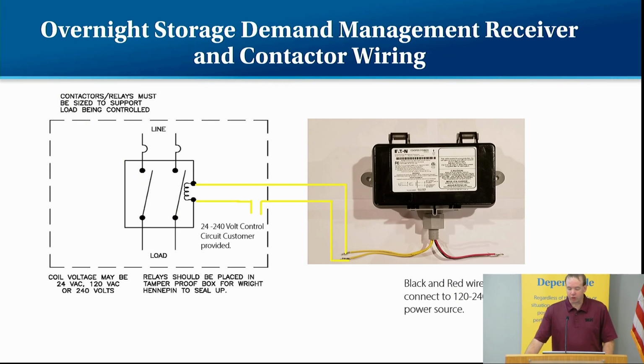So for the overnight storage, we have to add a demand management receiver and then the contactor. If you look at the diagram here, on the left side is the contactor provided, whether it's a 60 amp or 100 amp, depending upon the size of charger that's being installed. Our receivers require 120 to 240 volt power, so these usually work best if you're doing the CT metering. You already have the power at the meter. And then the yellow wires would go to the contactor to control the contactor.